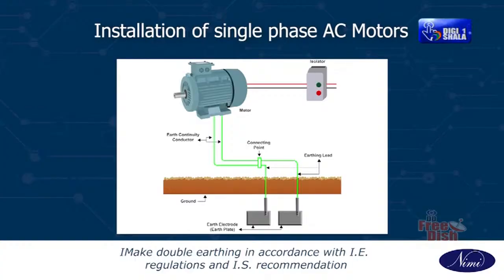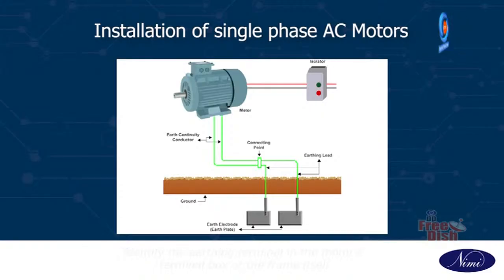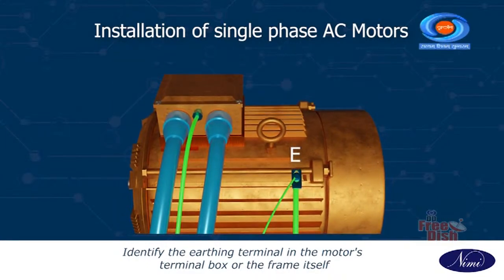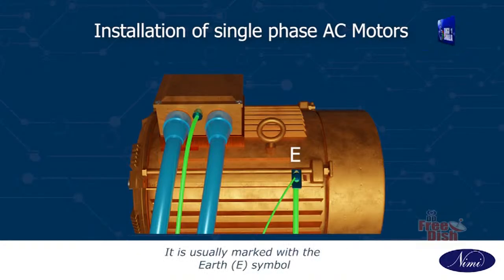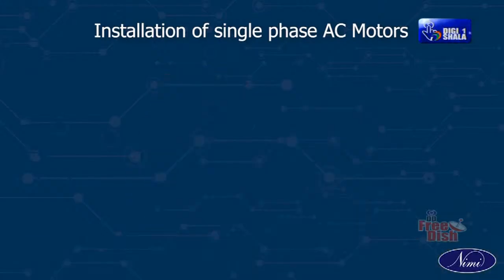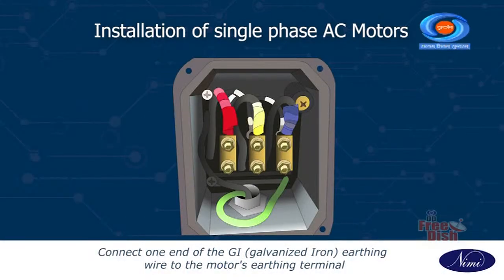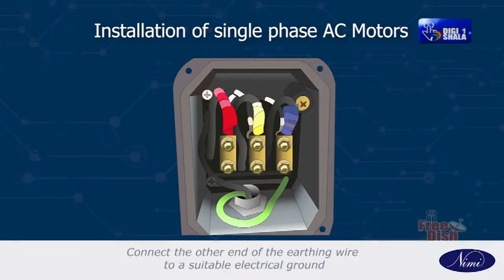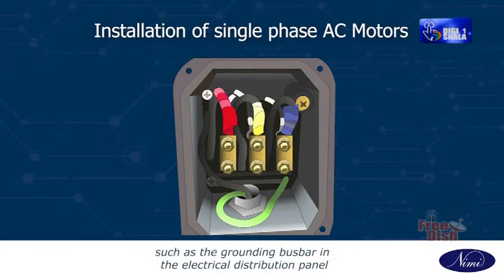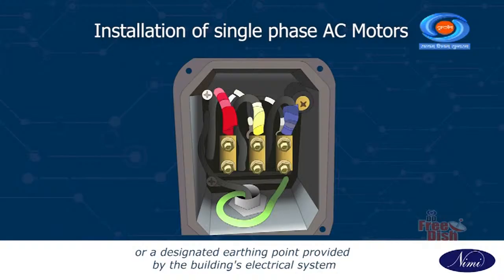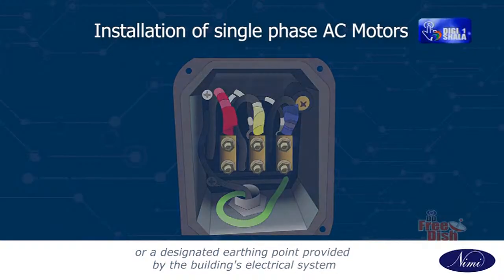Make double earthing in accordance with IE regulations and IS recommendation. 1. Identify the earthing terminal in the motor's terminal box or the frame itself. It is usually marked with the earth E symbol. 2. Connect one end of the GI galvanized iron earthing wire to the motor's earthing terminal. 3. Connect the other end of the earthing wire to a suitable electrical ground, such as the grounding busbar in the electrical distribution panel or a designated earthing point provided by the building's electrical system.